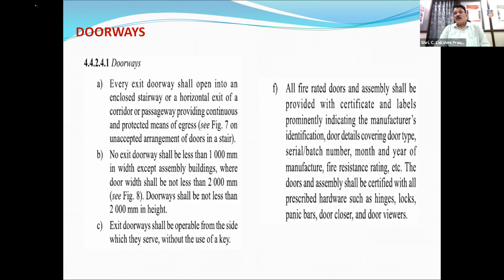Then even if you are having some assemblies in the door, they should also have 2-hour fire resistance. For example, you have a wooden door and the door has a glass panel. If the panel is 30-minute rated and the wooden door is 2-hour rated, then it is of no use, because after half an hour this glass will break and the smoke and fire will spread into the other areas of the building.